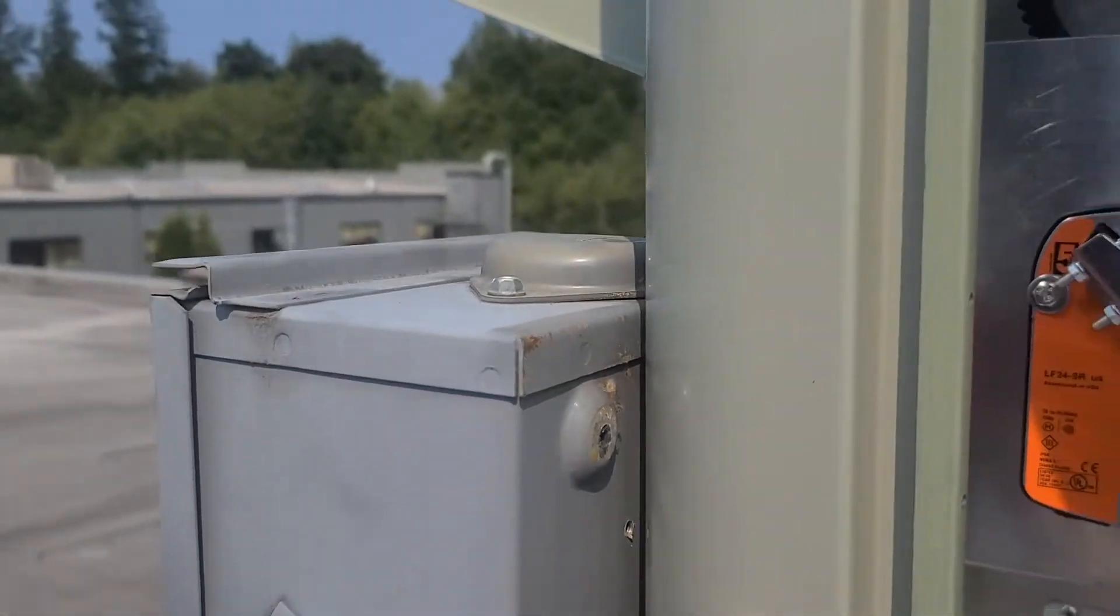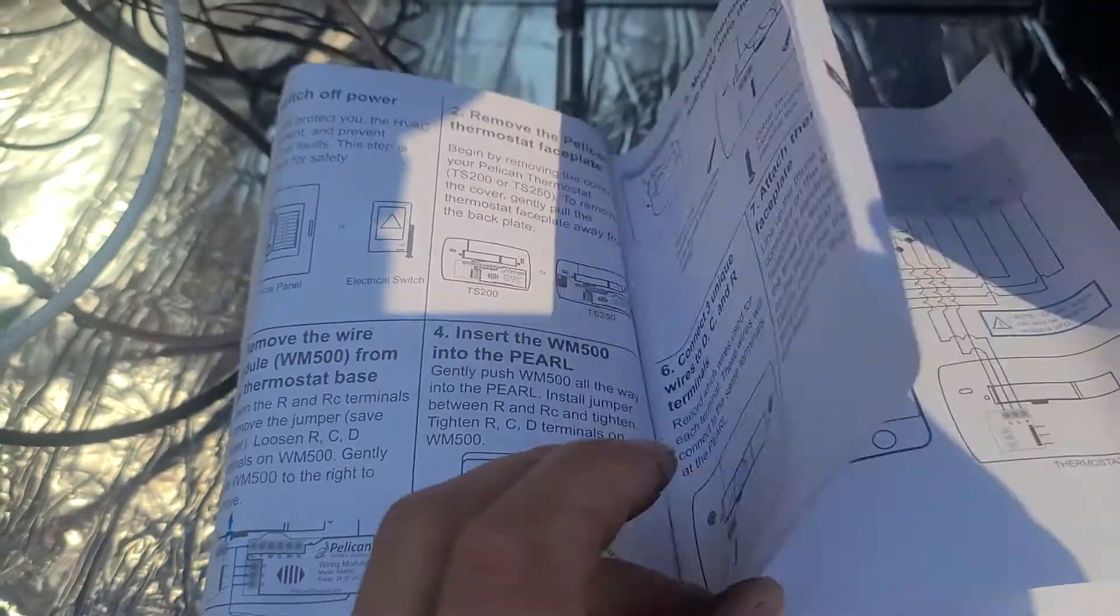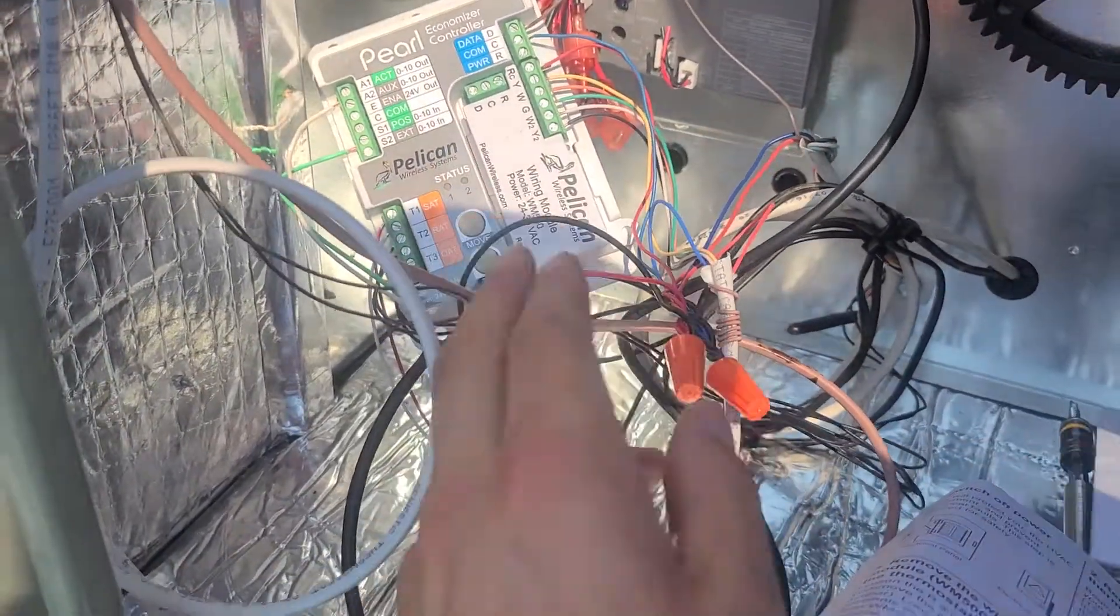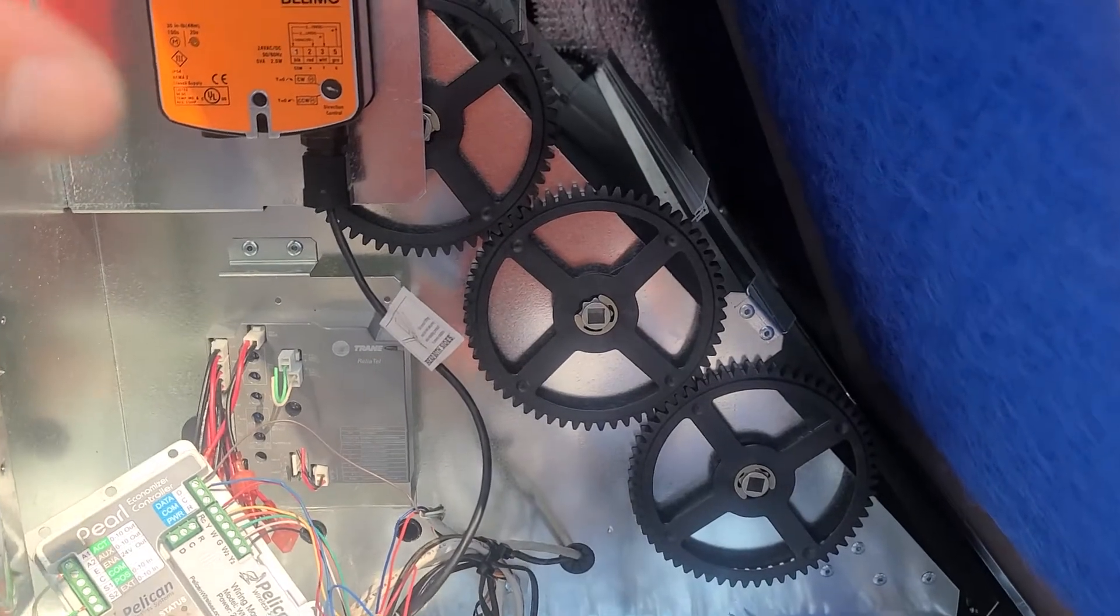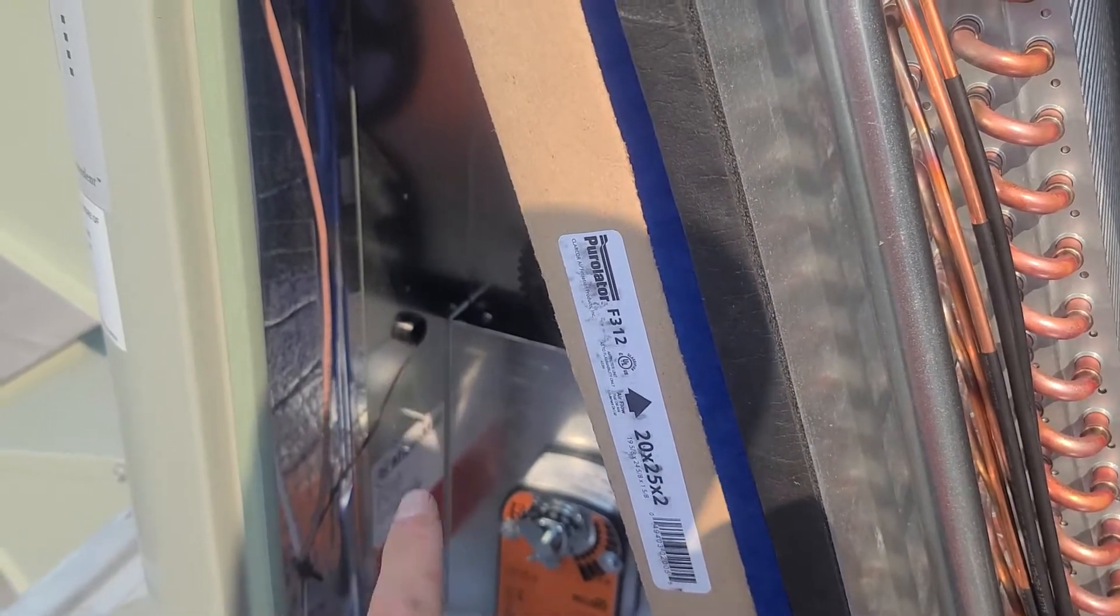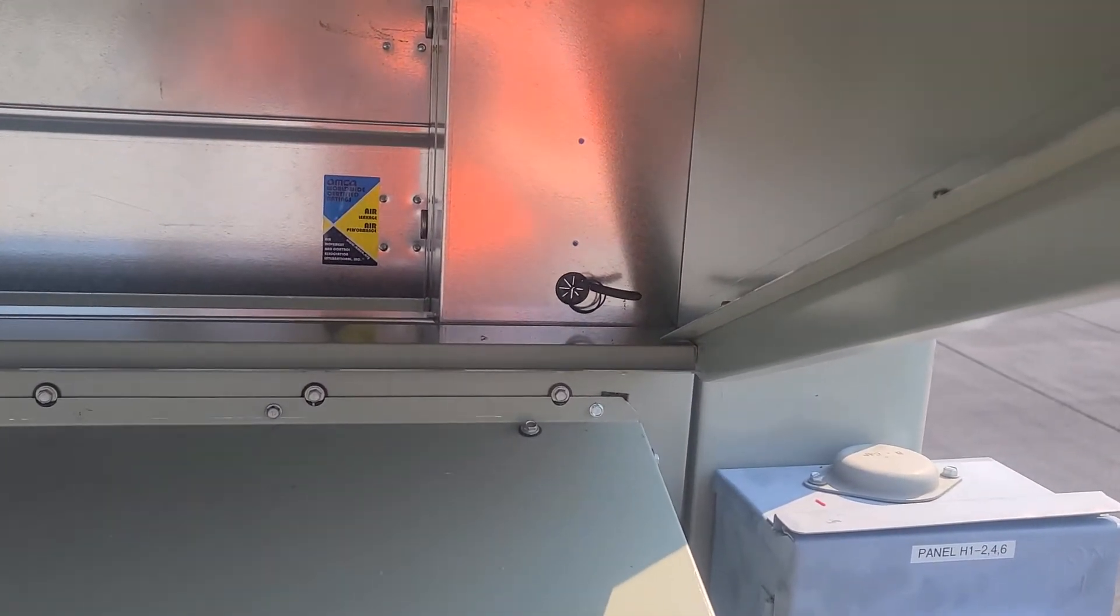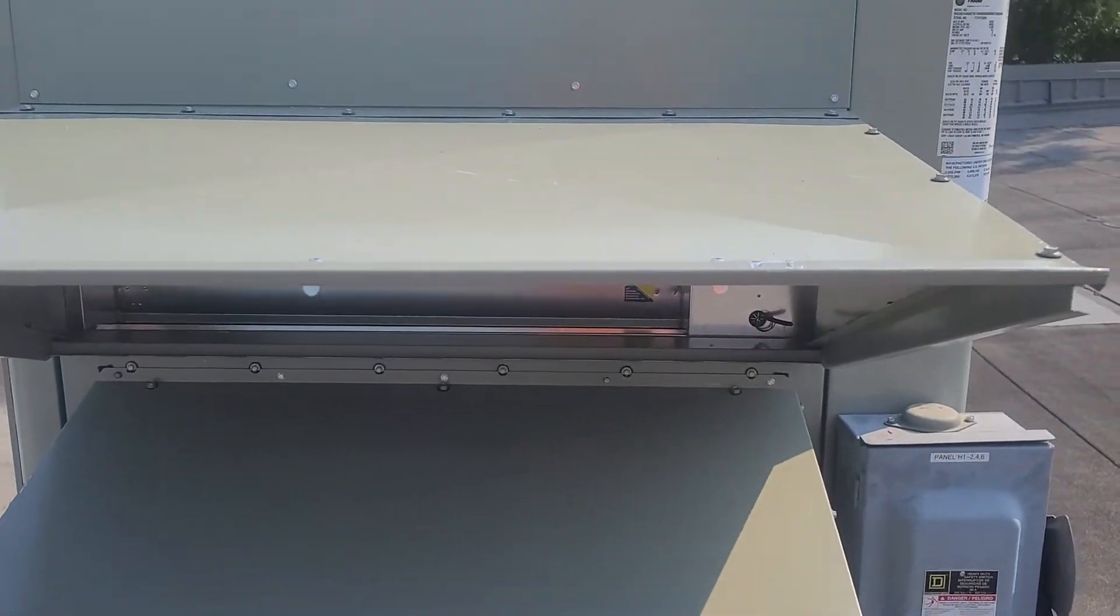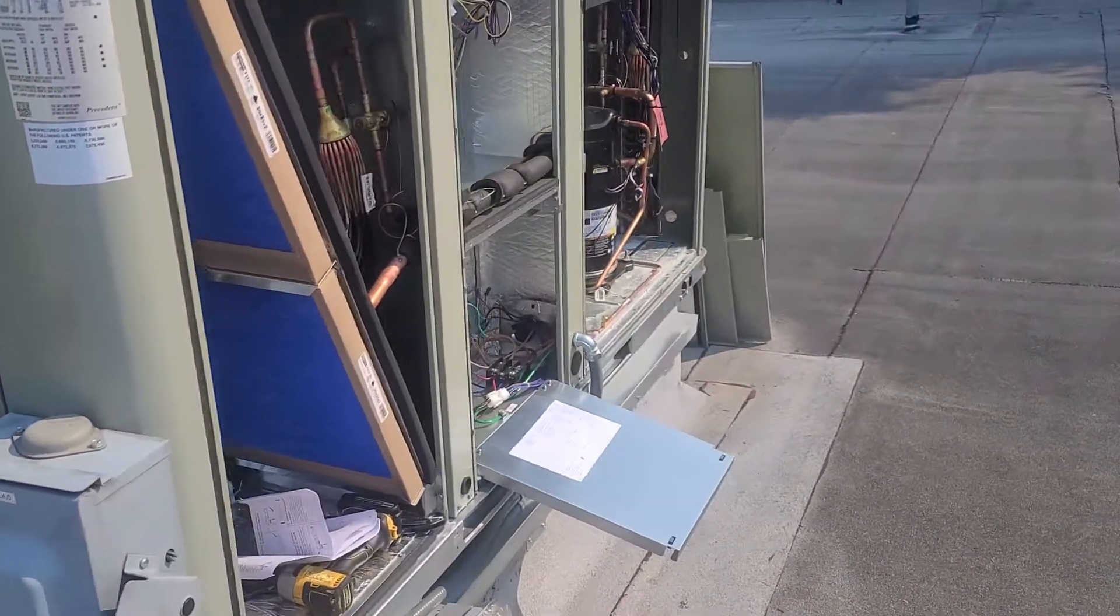For your outside air temp, you don't just want to drill a hole and stick it poking out where it's in direct sunlight or anything like that. They give you little decent leads on some of them, or you can run it right into this. Other ones you just have to run your own thermostat wire. I have a return sensor probe in my return, and then for the outside I always just poke it out. You can kind of see it right there. I just poke it out right to the outside air, and I'll probably throw a zip tie on that just to make sure it doesn't slide back out.